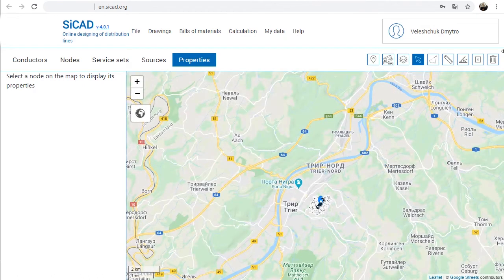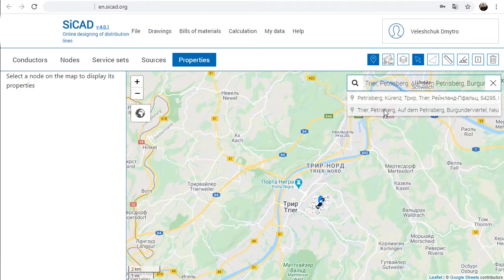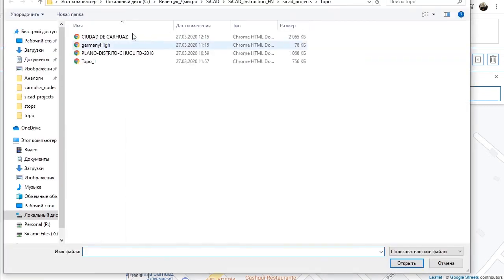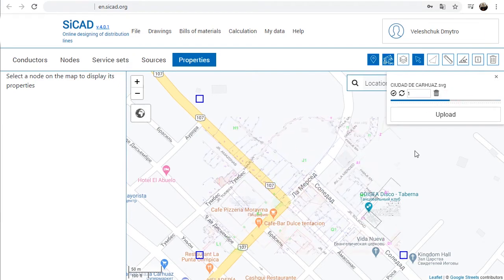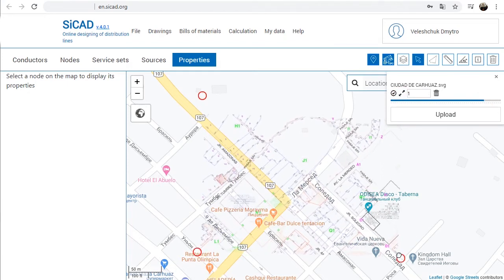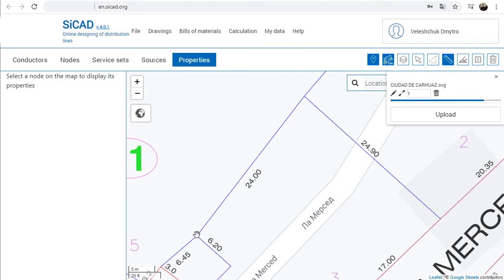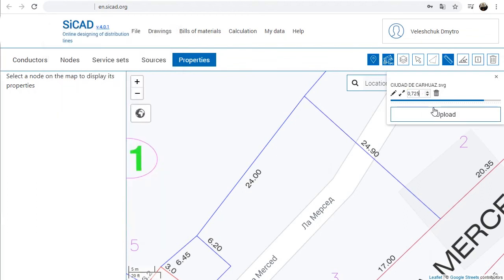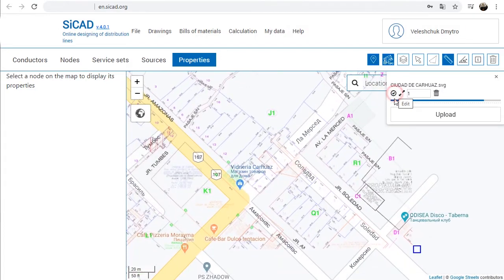During the design process, users have access to a toolbar. The Location Search tool allows finding a location on the map easily by entering a geographic name. The Topo tool allows downloading and displaying topographic maps in JPEG format or SVG vector format, and lets the user change position, size, transparency, and rotate the topographic map to match the online map if needed. For more precise scaling, use the zoom factor. To find the zoom factor, use the Ruler tool to measure the distance between points on the topographic map. The ratio between the actual distance value and the value measured by the Ruler tool will be the scale factor. After entering the scale factor, matching will be achieved and the user will obtain correct values of conductor lengths and specifications.